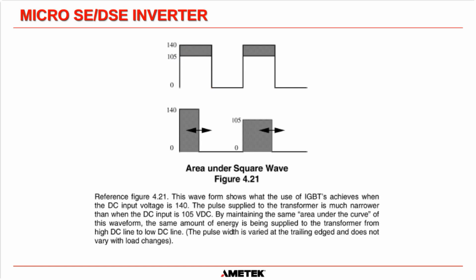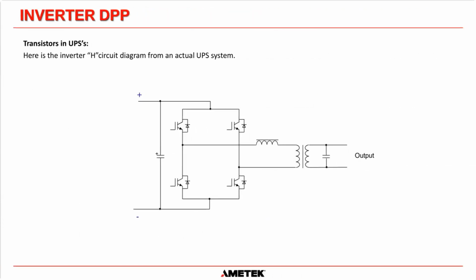So what we can do for 140 volts, if somebody puts a system in equalize, is switch off the IGBT sooner and keep the area under the curve exactly the same as it was for 105 volts. There we turn it on later, but if you did the math, the area under the curve here would be identical to this. The area under the curve on both of these is exactly the same. That is the only control of a square wave we have on a DSE system. The CVT or ferroresonant transformer does all of our current limiting and our voltage regulation. So that's our DSE system, our ferroresonant system.